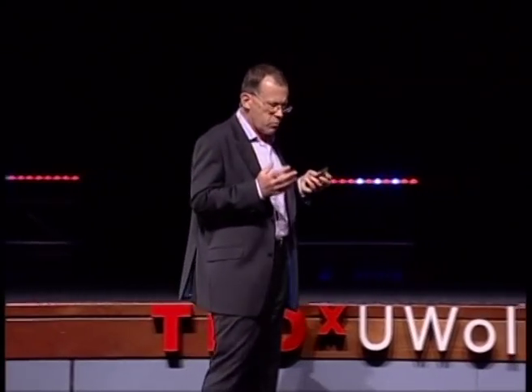These electrodes are in a planar fashion, and we've been working closely with retinal surgeons — because as noted, all this work has to be done in multidisciplinary groups — to develop a safe, effective way to perform surgery to insert these electrodes. The technique is to put a small incision in the sclera, then create a tissue pocket between the sclera and the blood vessels that feed the retina. The planar electrode slides down that tissue pocket to the back of the eye, and the sclera is sutured up, leaving only a lead wire exiting from the eye back to the implantable stimulator.